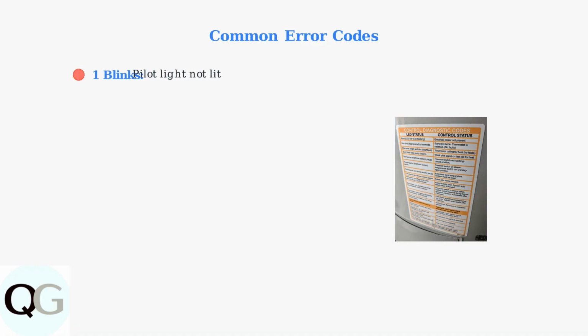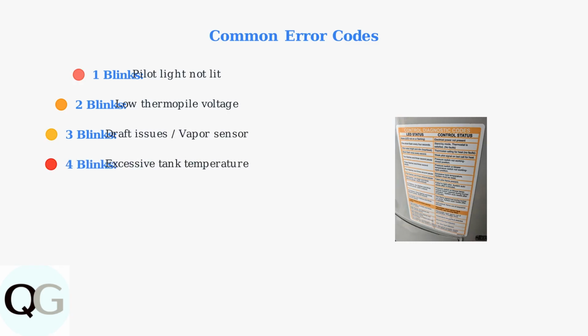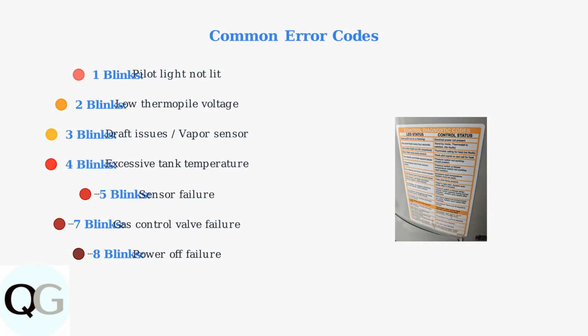One blink indicates the pilot light is not lit or has gone out. Two blinks mean low thermopile voltage, often due to loose wiring or a failing thermopile. Three blinks indicate draft issues or flammable vapor sensor activation. Four blinks mean excessive tank temperature, which could indicate a faulty thermostat. Five blinks indicate sensor failure requiring replacement. Seven blinks mean gas control valve failure, and eight blinks indicate a power-off failure requiring system reset.